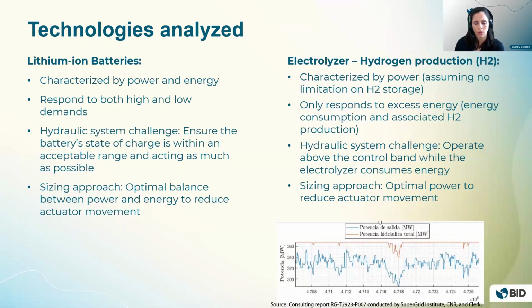The figure below on the right shows how the hydraulic system generally remains at constant power, that's the orange line, while the electrolyzer handles most of the frequency regulation, that's the blue line you can see. Only when frequency deviations are too large to be managed by the electrolyzer alone, the hydraulic system completes the plant's response. With electrolyzers, what you have at the end is that you will have less electricity injected to the grid as it will be used for hydrogen production.